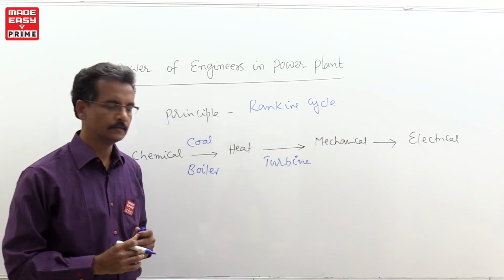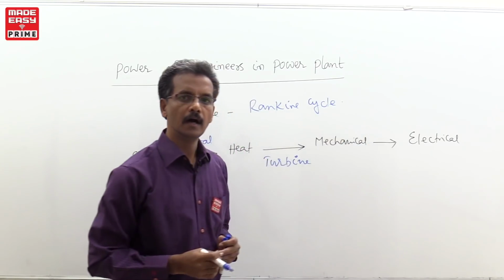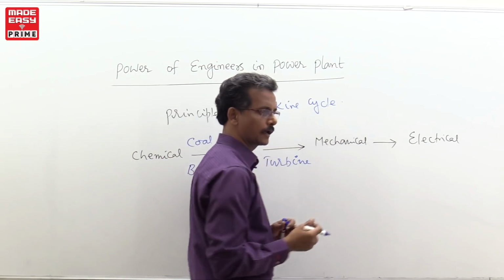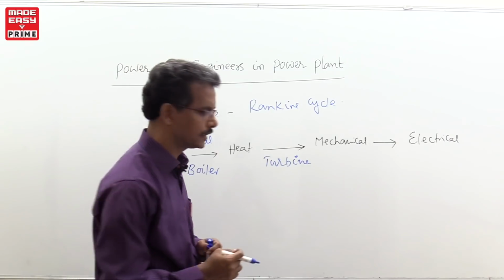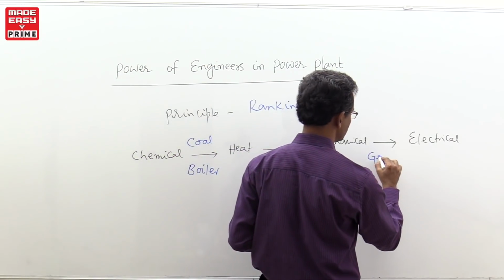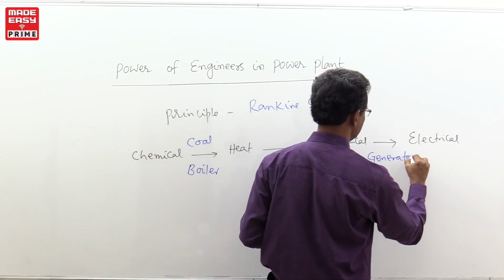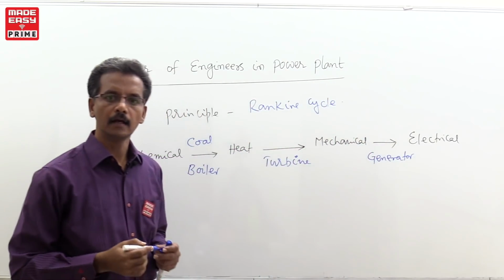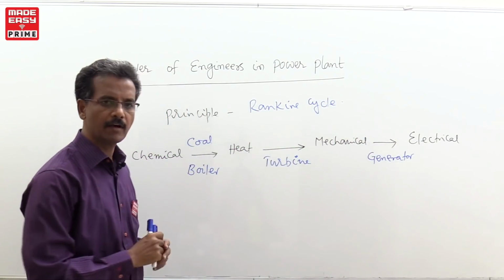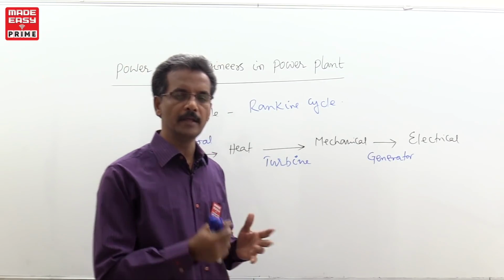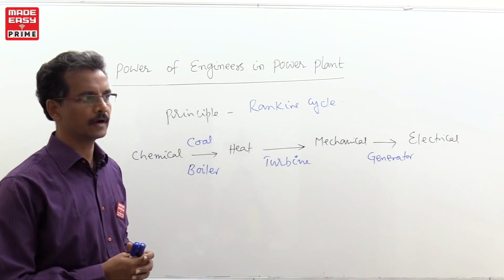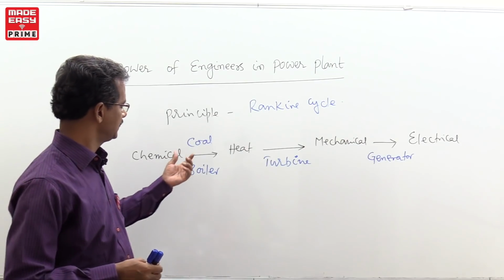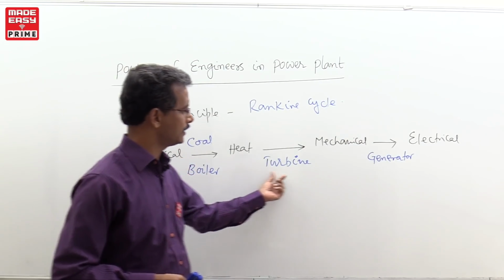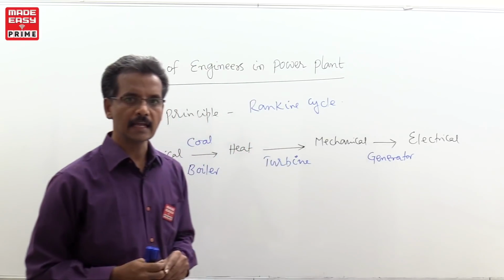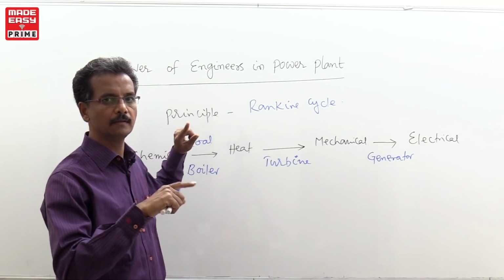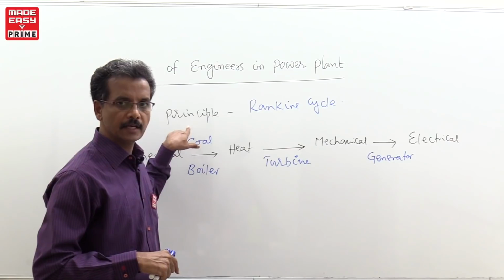This mechanical power is connected, this turbine is coupled to the generator. This generator will produce an electrical output, converting mechanical output into electrical output. So the basic requirement for a thermal plant like a coal based plant, and also in the case of a gas based plant, is what? A boiler, a turbine and a generator. Think of a gas based plant: instead of coal, gas is used.